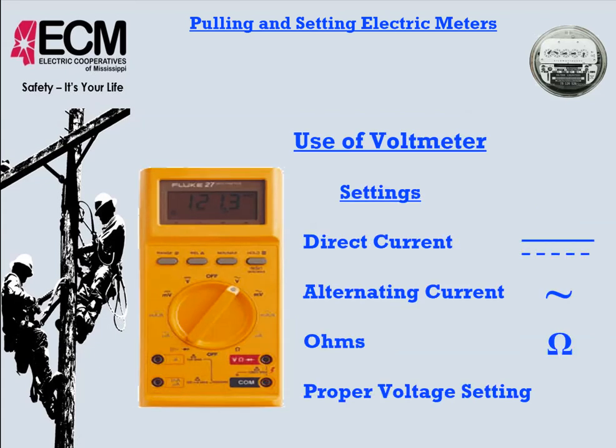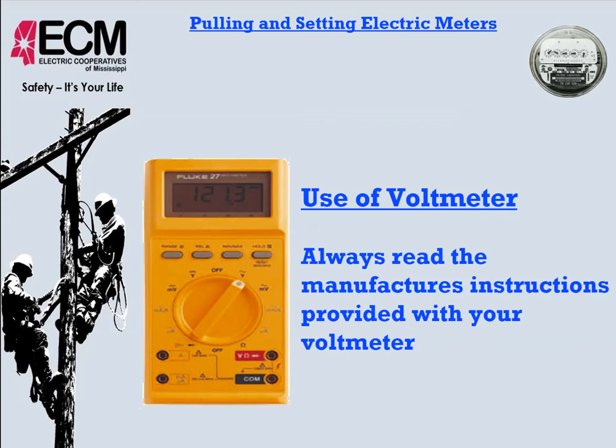Okay. The settings: direct current, which we very rarely use, will be depicted either by a DC or a solid straight line, or a broken straight line. Alternating current will be designated by an AC or a sine wave, and then ohms will either say ohms or have an omega symbol, making sure that whatever you are testing or measuring, your voltmeter is set to the proper setting. Now, if something is energized, you should never check for resistance. This will cause catastrophic malfunction and failure of your multimeter. Okay? Some meters have protection for it, but most do not. So there again, always read the manufacturer's instructions of the voltmeter to ensure that you're using it in the proper way.